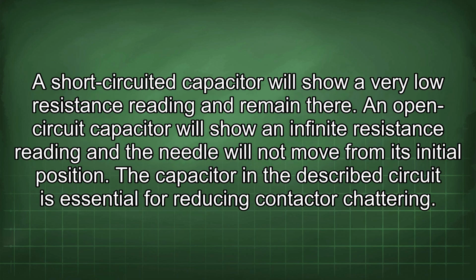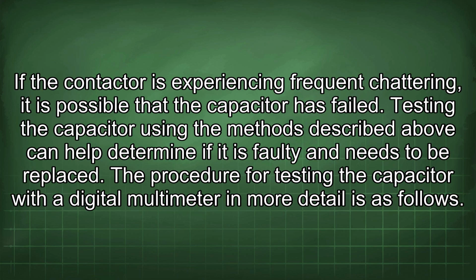A short-circuited capacitor will show a very low resistance reading and remain there. An open-circuit capacitor will show an infinite resistance reading and the needle will not move from its initial position. The capacitor in the described circuit is essential for reducing contactor chattering. If the contactor is experiencing frequent chattering, it is possible that the capacitor has failed. Testing the capacitor using the methods described above can help determine if it is faulty and needs to be replaced.